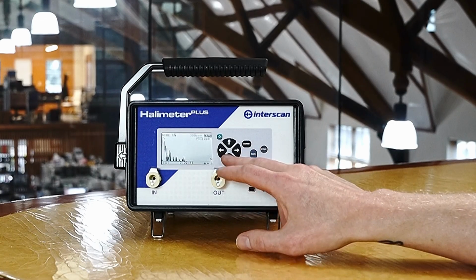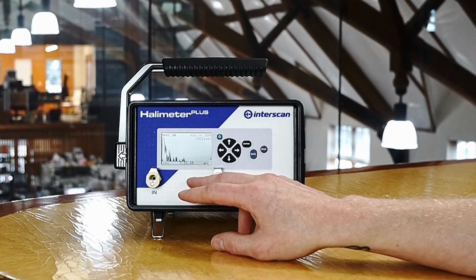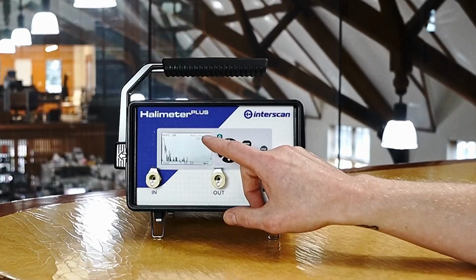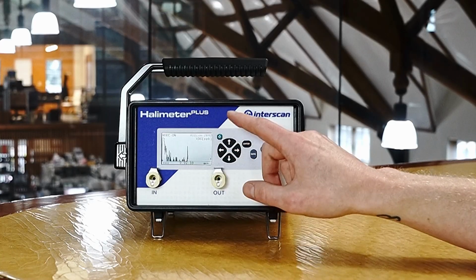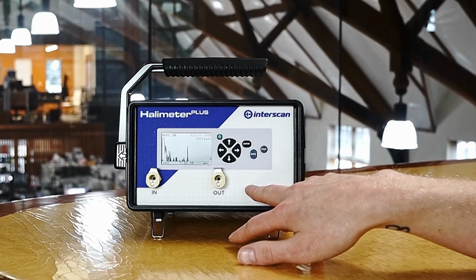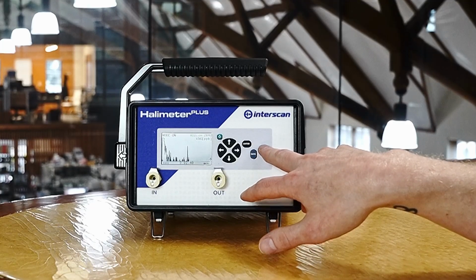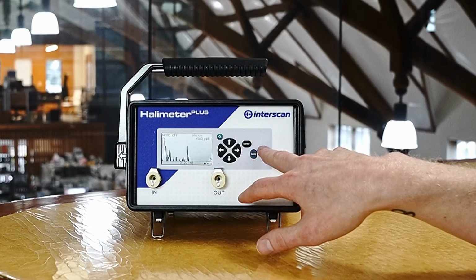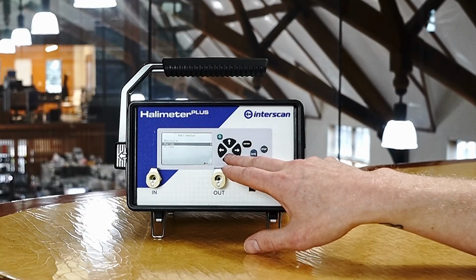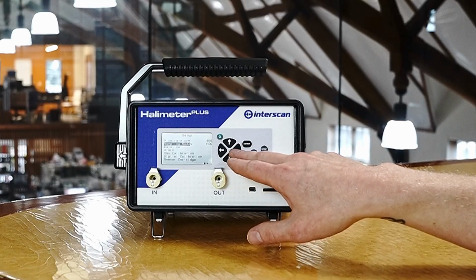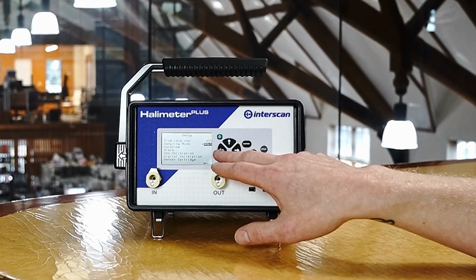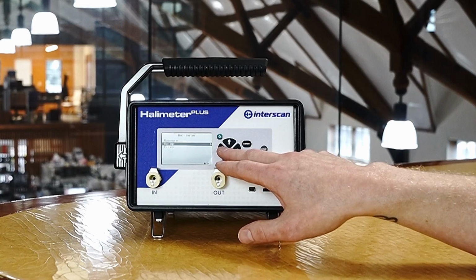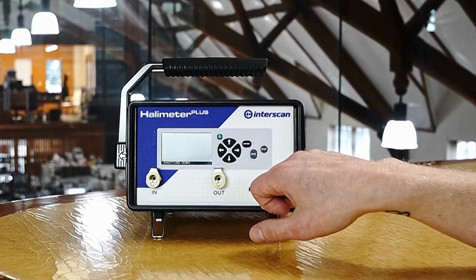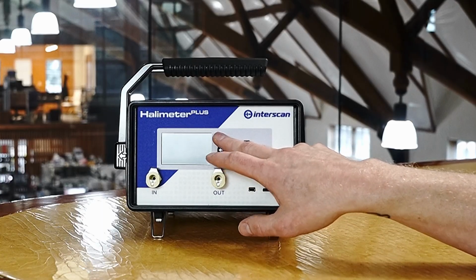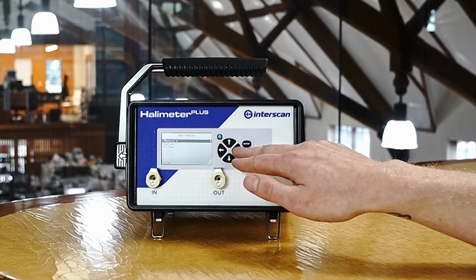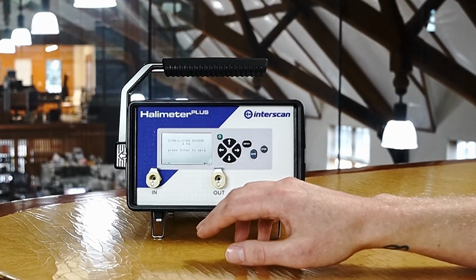I'd like to show you the different sampling modes available. Currently I have constant sampling mode on, and you can see the pump is running with continuous measurements taking place. If you require breath measurements, stop the pump by hitting stop, then navigate out to the main menu — you can hit stop again. Go down to setup, then change your sampling mode to Halimeter mode. To save this mode, you have to power off the device and power it back on. When you go back into measure mode, it will show your sensor stabilization menu again.